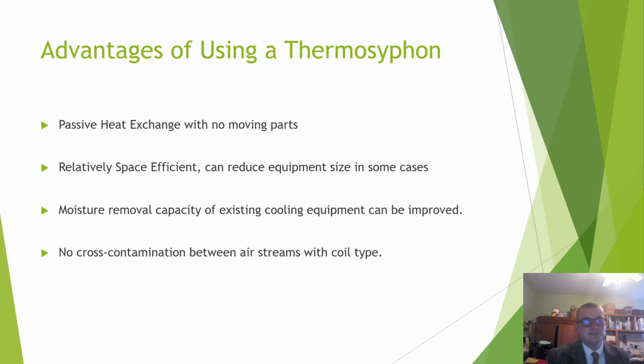Advantages of using a thermosiphon. A thermosiphon is a passive heat exchange with no moving parts. It is relatively space efficient and can reduce equipment size in some cases. Sometimes the AC system is ridiculously larger than it has to be, and sometimes a thermosiphon system will reduce it significantly. The moisture removal capacity of existing cooling equipment can be improved with thermosiphons.